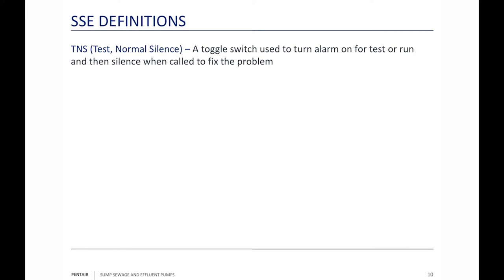TNS is a similar double-throw toggle switch with three settings. Test means you're checking if the alarm system works. Normal means the float determines when the alarm turns on and off. S means you're at the job site and the noise is so loud you can't stand it — you flip to S and that silences the audio part of the alarm. The visual indicator (red or amber light) still works, but the horn is turned off.